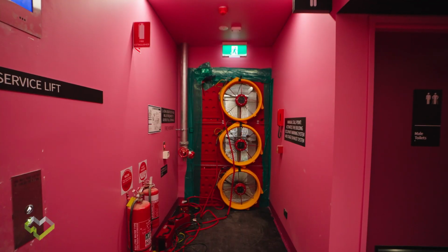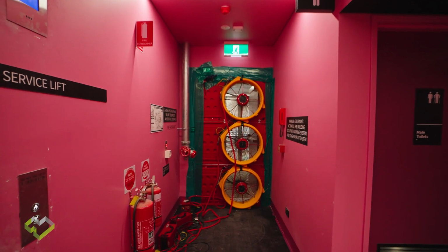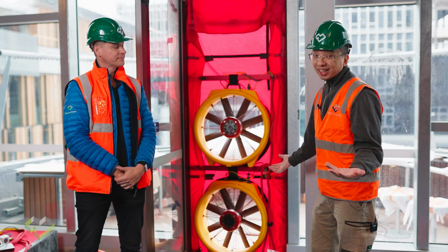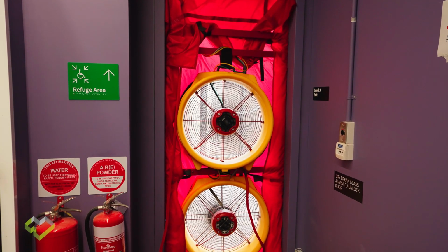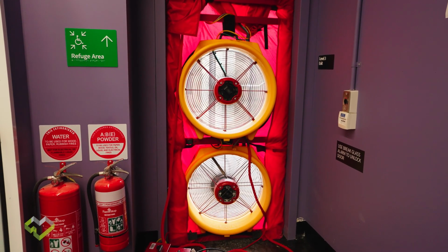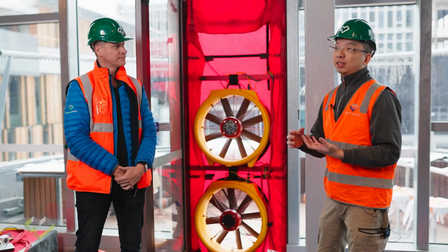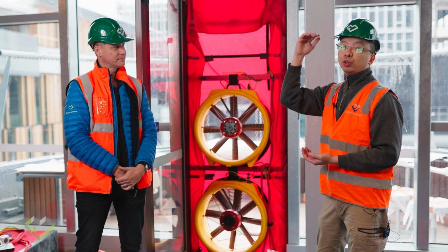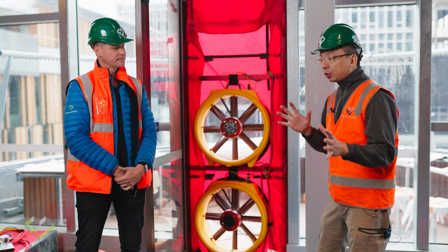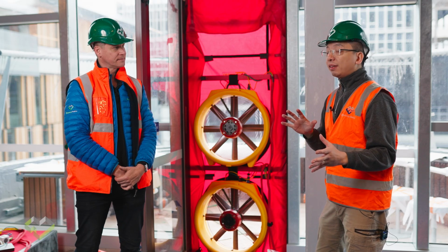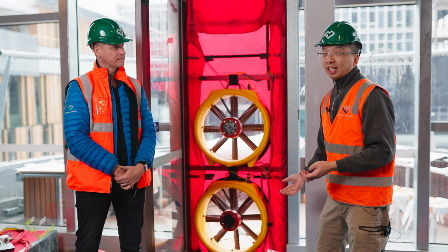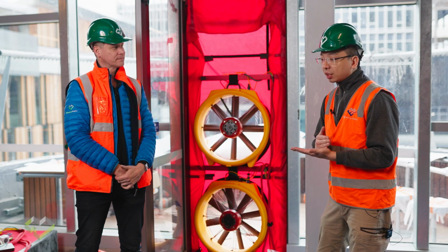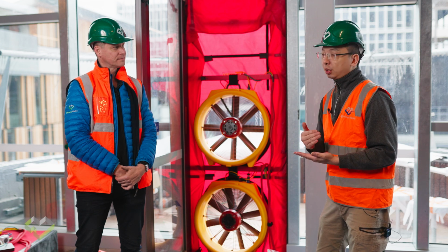And the wind can have a detrimental effect because it can be directly competing with our fan on one hand. On the other hand, it may create an uneven drag of air in different portions of the building. Usually wind has a higher effect near the roof level. So we need to balance out the effect of wind with our fan, and it makes the whole process a lot more difficult, and it's harder to get reliable and repeatable results.